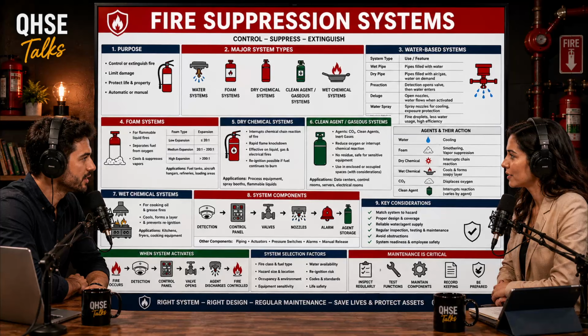You mentioned the specific temperature. The sprinkler heads are color-coded based on that activation temperature, correct? This seems like prime material for an exam question. Oh, it's highly testable. Safety professionals must know them. An uncolored or black frame or an orange or red glass bulb indicates an ordinary temperature rating of 135 to 170 degrees Fahrenheit. Okay, that's standard.